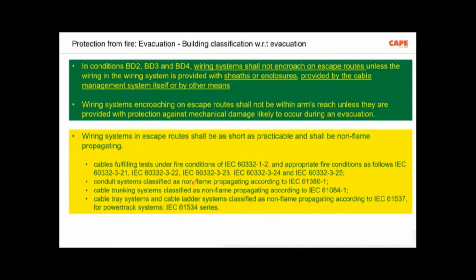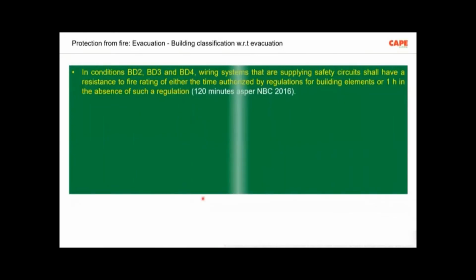Wiring system in escape route, actually the wires and the wiring fixing materials have to satisfy some special requirements, especially on escape routes in buildings BD3 and BD4, because the escape route is not supposed to have a fire or smoke up to 120 minutes during evacuation, or up to a certain time during evacuation. I'm just showing you some of the requirements. I didn't put all the requirements here.